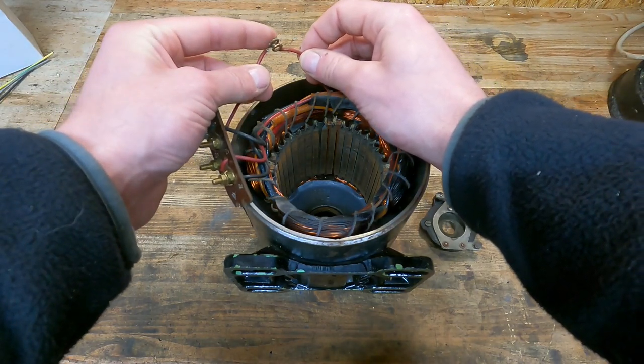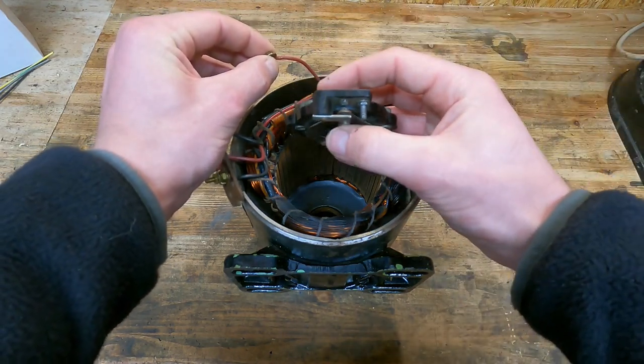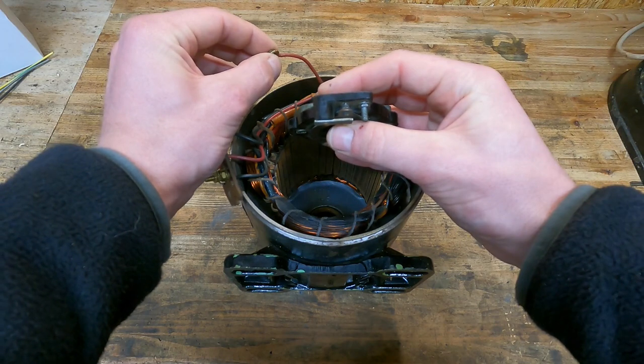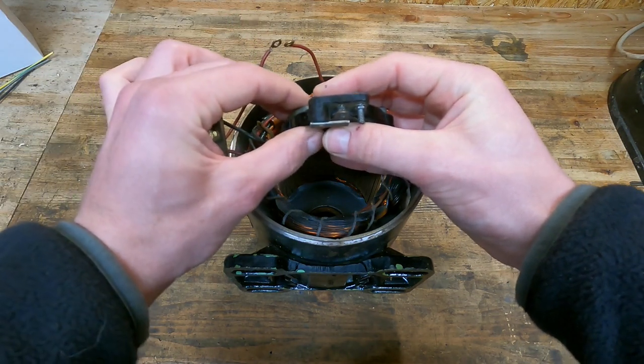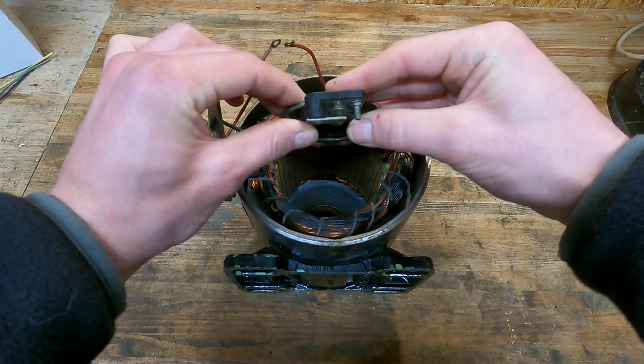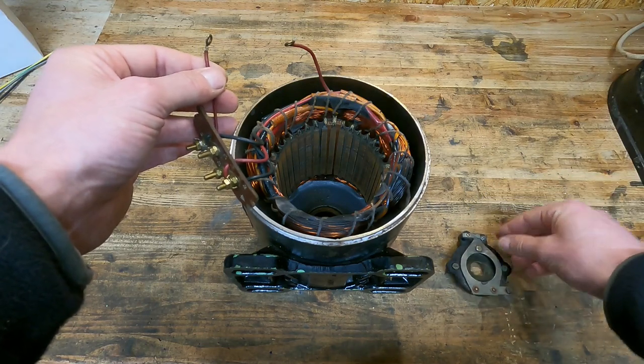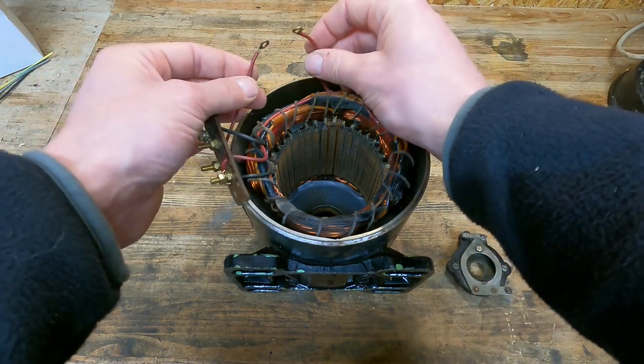These two cables on the start winding are normally joined by the centrifugal switch. This is the start position for it. As the motor gets up to speed, the centrifugal switch allows this to open up, which disconnects these two cables and stops power going to the start winding.